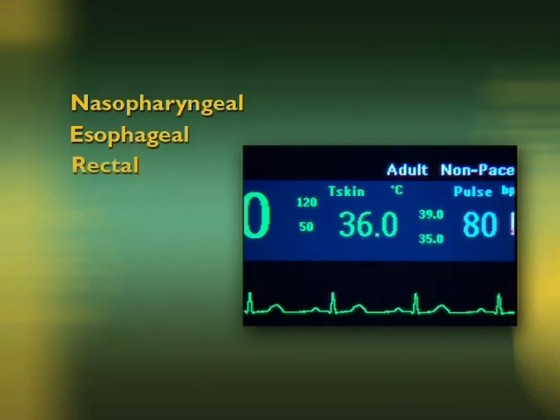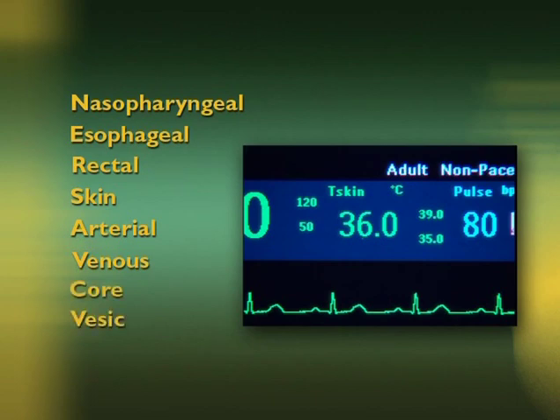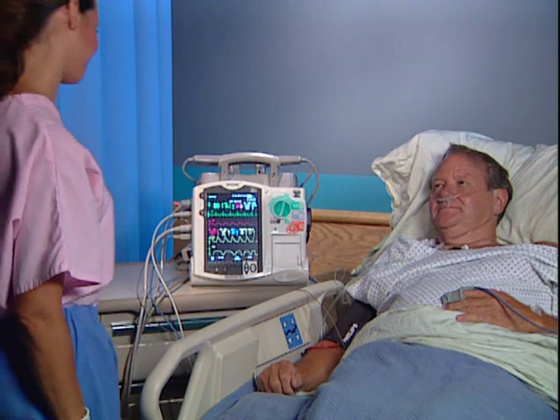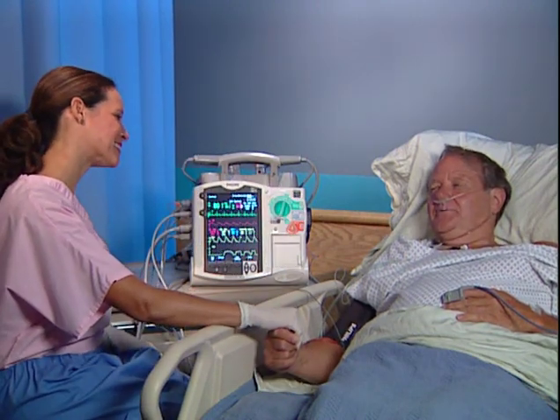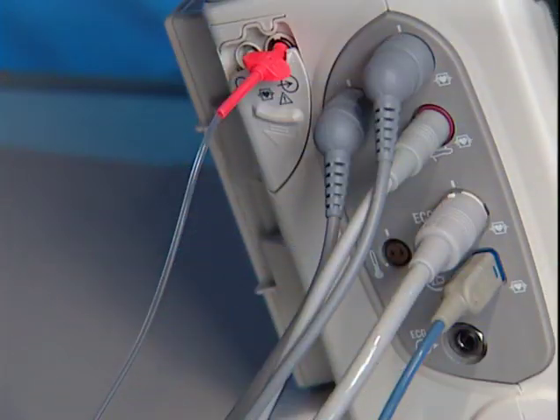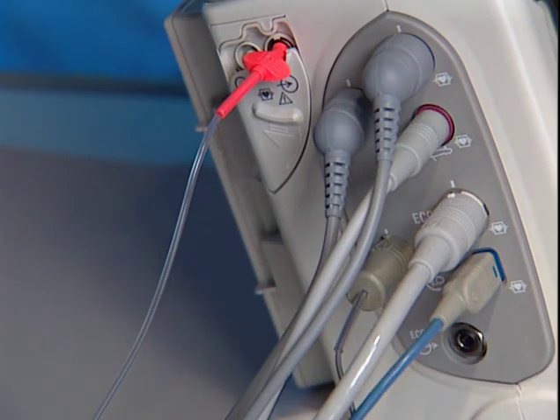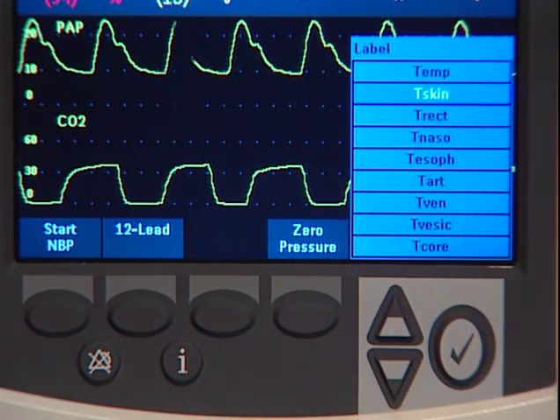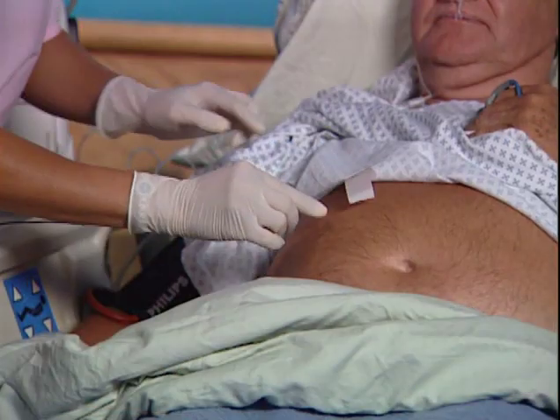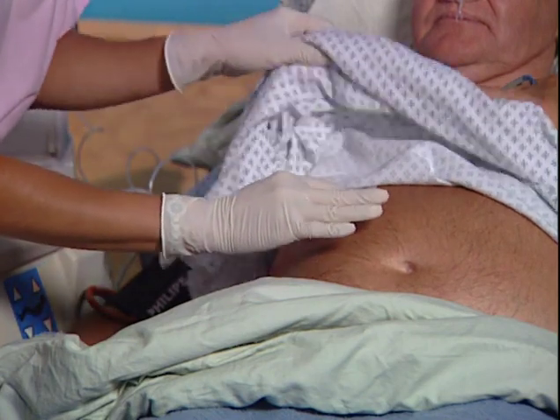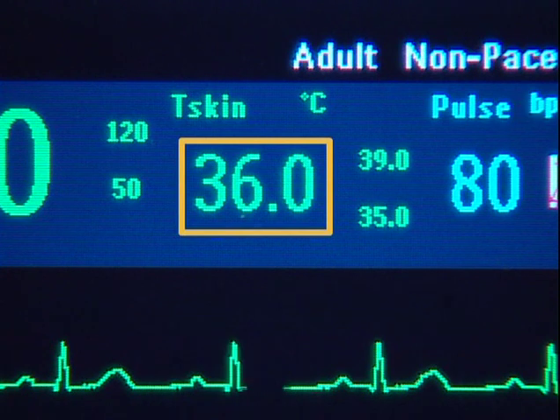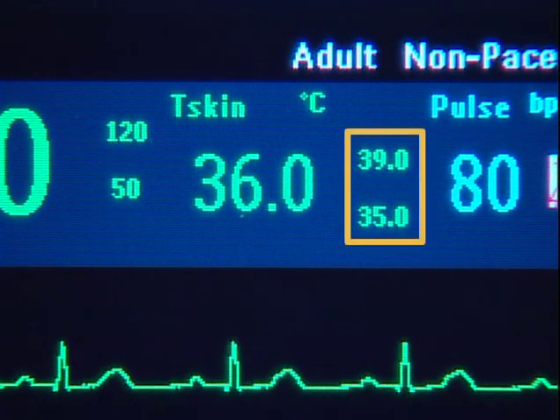The HeartStart MRx provides real-time, continuous temperature monitoring using nasopharyngeal, esophageal, rectal, skin, arterial, venous, core, and vesic, or urinary bladder temperatures. Measurements can be displayed in either Fahrenheit or Celsius and may be taken while in monitor, including 12-lead, pacer, or manual defib modes. To monitor temperature, connect the temperature cable to the HeartStart MRx. Select the correct temperature label for your measurement. Apply the temperature probe to the patient. The continuous reading appears on the screen. Check that the current alarm settings are appropriate for the patient.